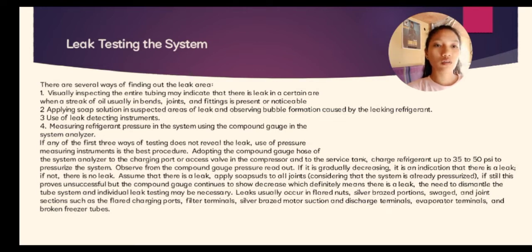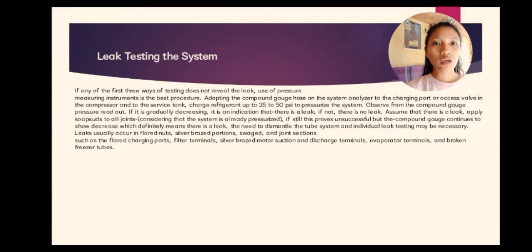Leaks usually occur in the flared nut, silver brazed portion, swage, and joint sections that have the flared charging ports, filter terminals, silver brazed motor suction and discharge terminals, evaporator terminal, and broken freezer tube.